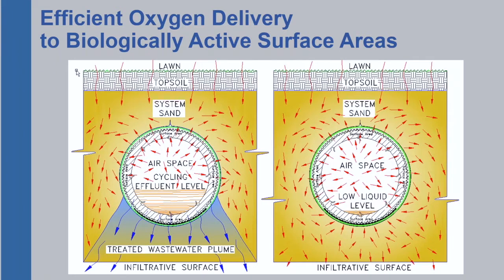Regarding the venting system: when a dose comes in it fills the pipe, distributes along the length, and infiltrates into the soil. When the dose goes away, air comes back in to fill that void. The large open space of the pipe provides lots of provision for air and oxygen to supply the microbes. This reduces clogging by providing more oxygen. It's just an enhancement of a sand filter.